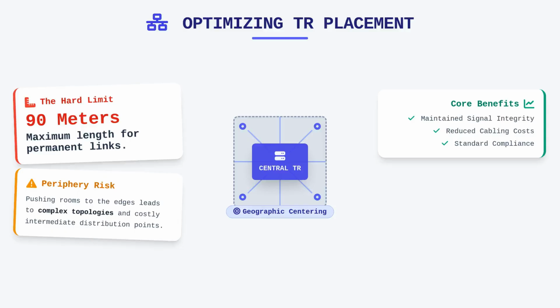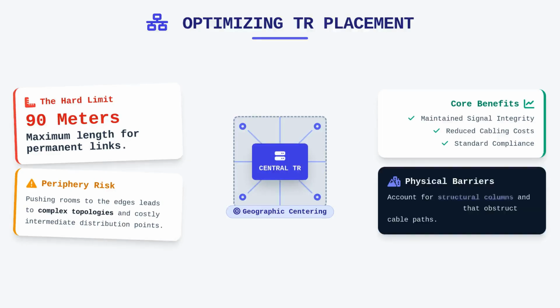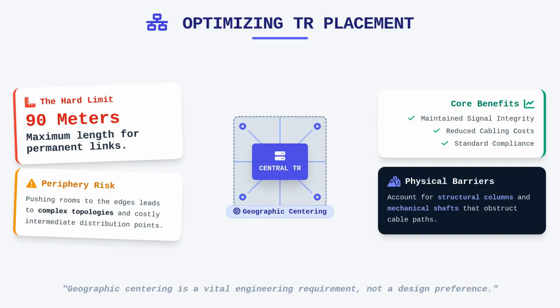You should map your floor plan meticulously, measuring the distance from the room to the furthest outlet in every quadrant to ensure compliance with relevant standards. Geographic centering is not merely a design preference, it is a vital engineering requirement to ensure that no drop exceeds the rigid distance thresholds established by current telecommunication standards. Consider how structural columns or existing mechanical shafts might obstruct your cable paths, as these elements often dictate the final, practical boundaries of your telecommunications room.